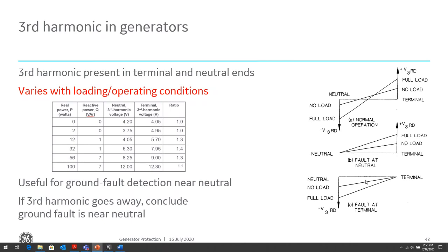And similarly at the terminal, if you have a ground fault at the terminal, that linear distribution of the third harmonic voltage starts at the terminal, where it is now 0. So hence, that's why we can use the 27 third harmonic undervoltage element to determine faults within the neutral or the terminal of the generator, because if the fault is at the neutral, the third harmonic voltage will drop. If the fault is close to the terminal, the third harmonic voltage will drop. So if the third harmonic goes away, we can conclude there's a ground fault, depending on where we're reading it, at the neutral or the terminal side of the transformer.